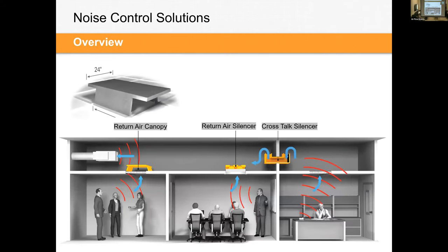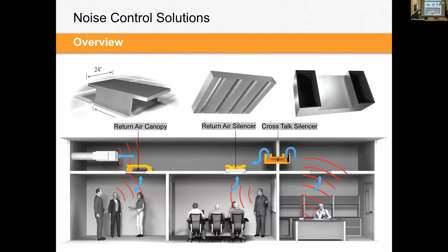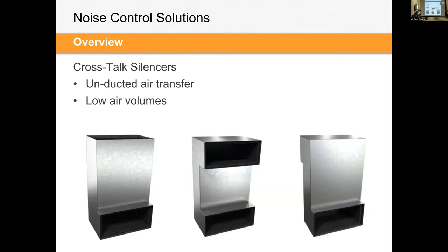There's three main types of air transfer silencers: the return air canopy or the rack, the return air silencer, and the crosstalk silencer. And really, the intention with these products is almost acting like a return grill accessory, a return grill silencer. So on the wall here, there's a couple wall returns, it appears. This is where those products would go, in behind that diffuser grill sort of air transfer device.